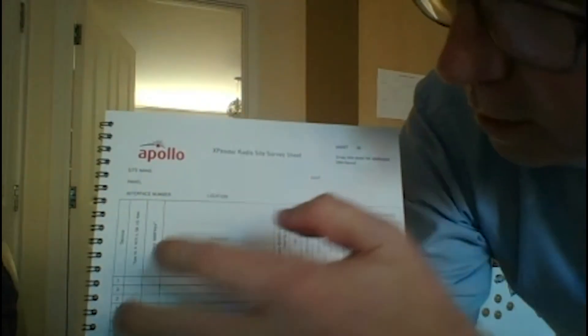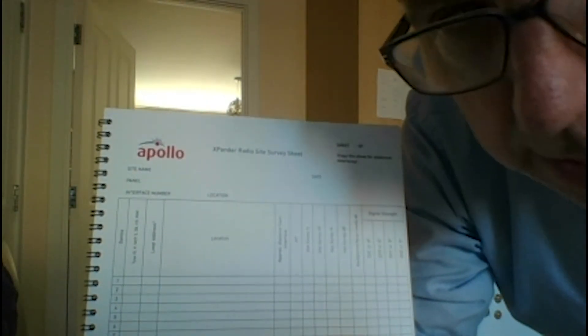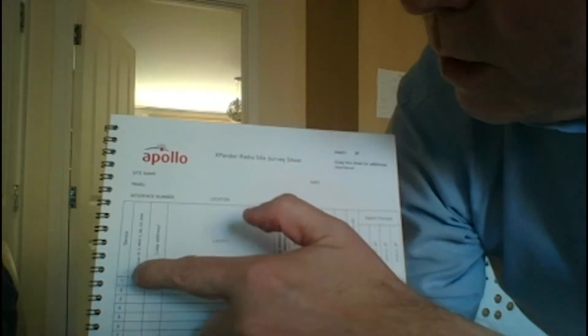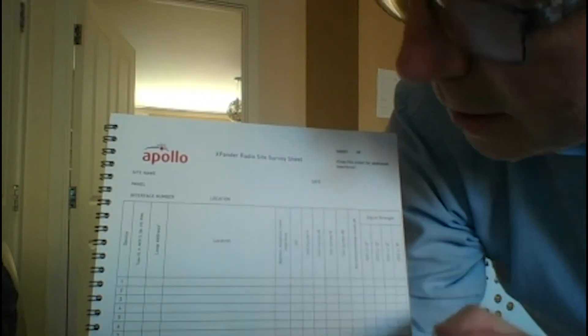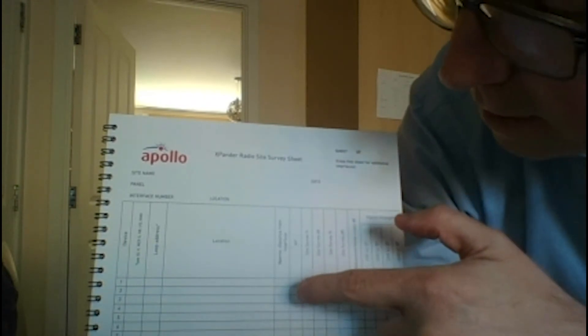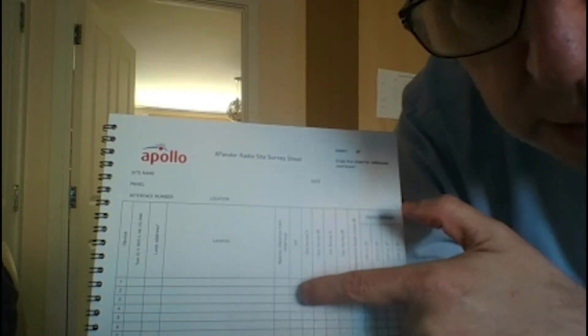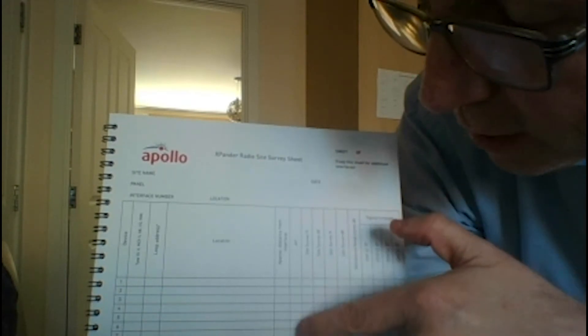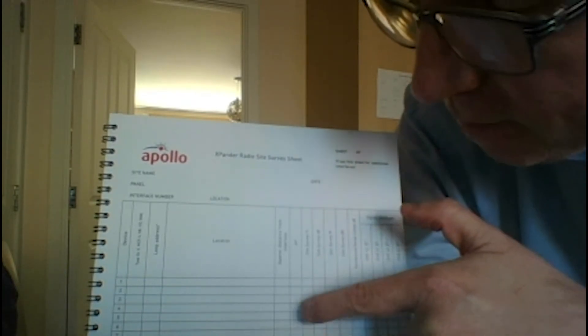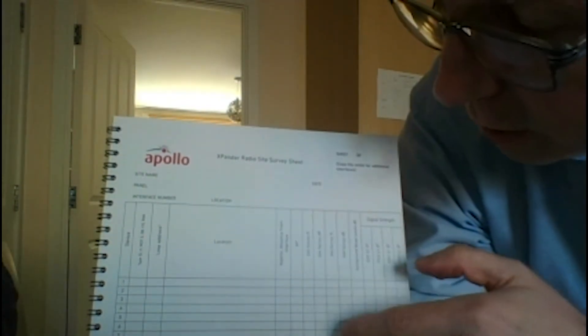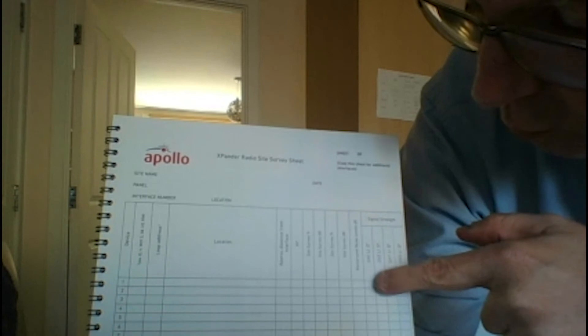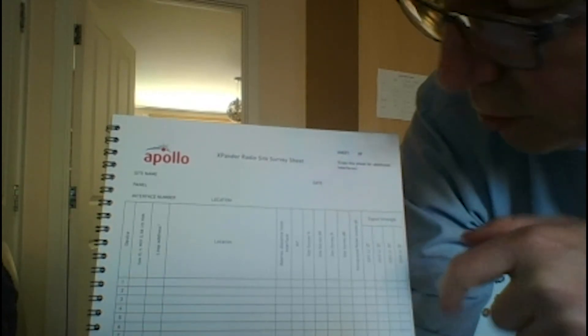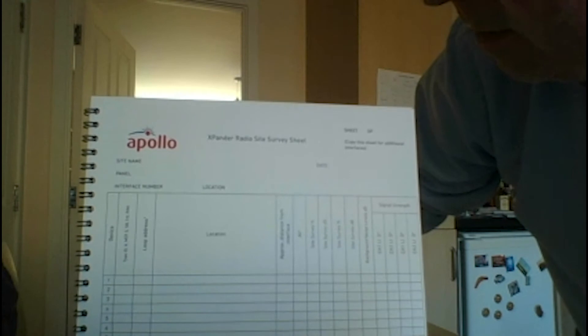Now the other boxes that are on here you'll probably fill in at a later time. So you've got a loop address - you might put that in now but probably put that in later. The analog value you would probably put in later, and you get that off the main fire control panel. And all the analog values are listed in this commissioning guide, and you've got all these signal strength levels which you can also take.